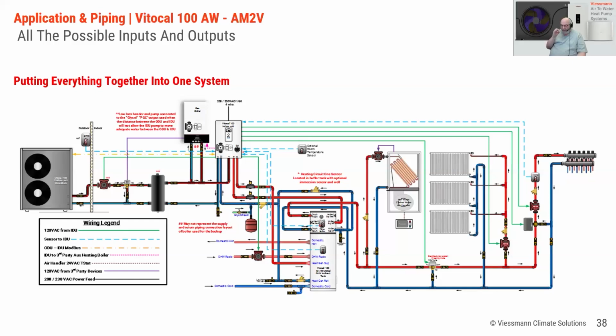Yeah, but only below that heat enable point, the electric heat enable point. Correct. In the middle of summer, you really shouldn't need the electric elements to come on. You're going to make DHW real fast when it's hot out. The buffer tank size is, like I said, 75 liters, or just about 20 gallons. So you have to look at your system design and say my air handler is going to use so many GPM, decide how long your tank is going to take to recover, and decide whether that buffer tank is large enough for that application.